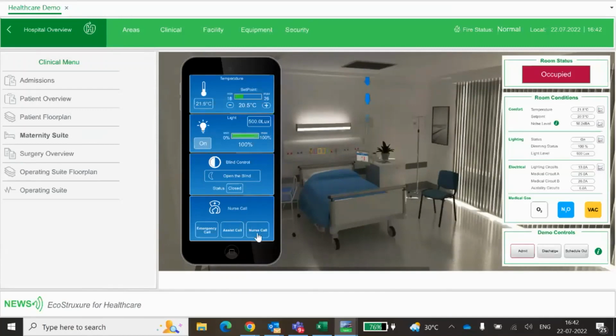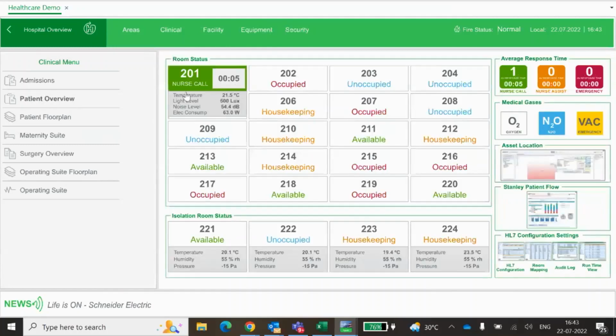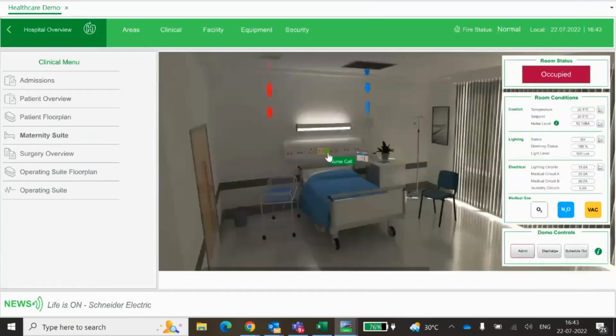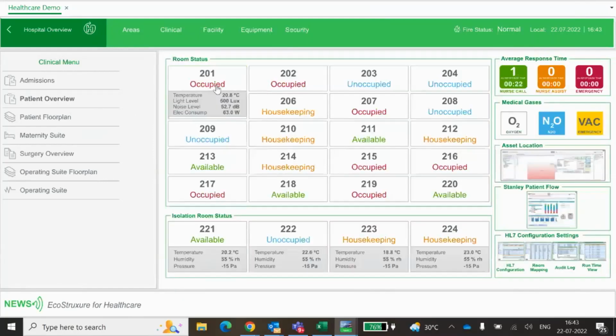Second is integration with the nurse call system. If that is integrated with the BMS, the patient can press the nurse call button, and on the user interface it will show that room number 201 the nurse is calling. A timer starts to indicate how fast the nurses are responding. Once the nurse goes to the room and presses the button, the counter stops, showing she responded within 22 seconds.